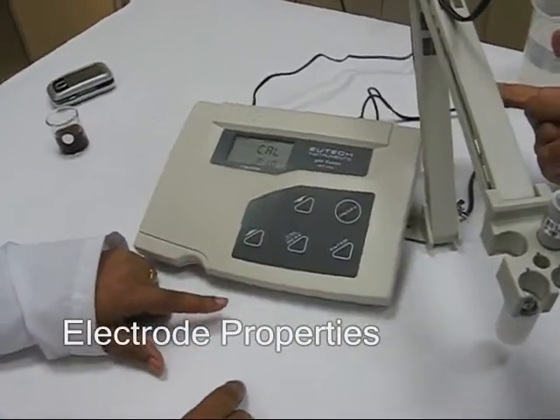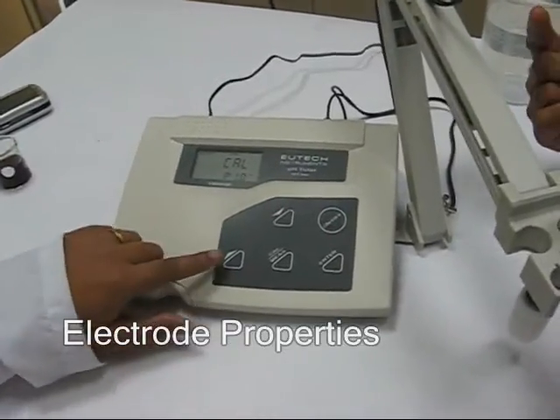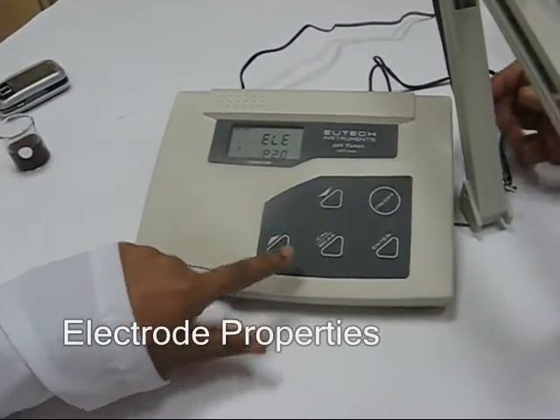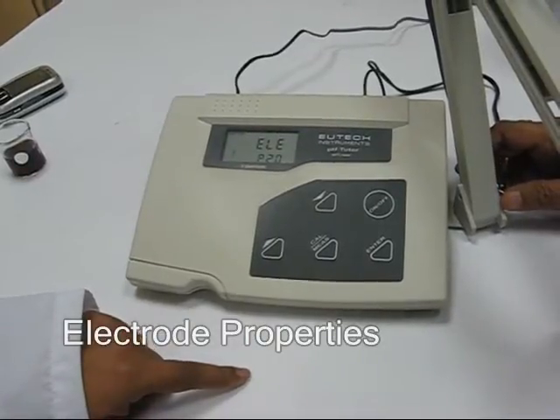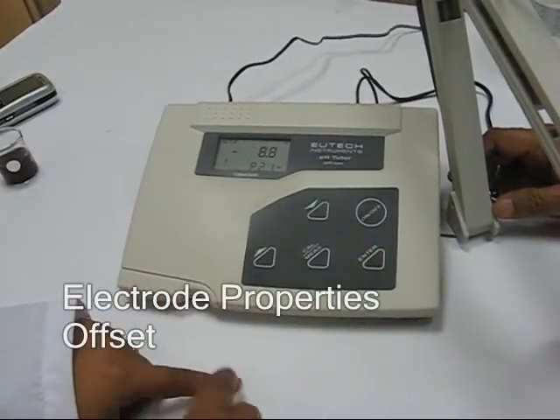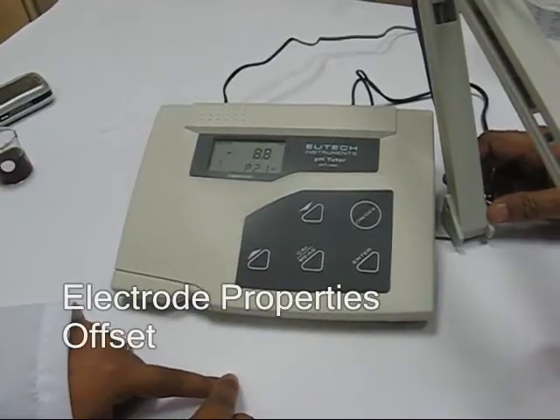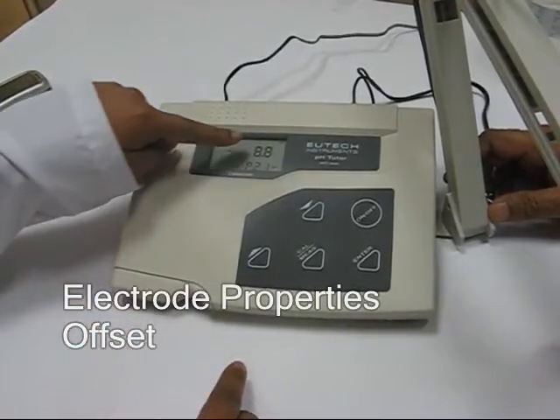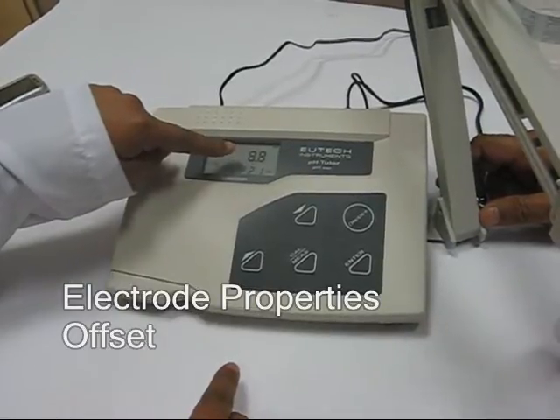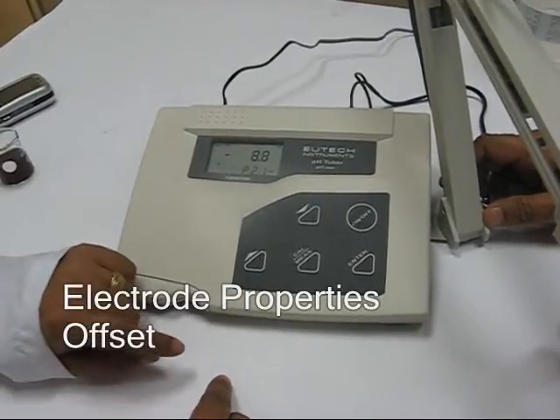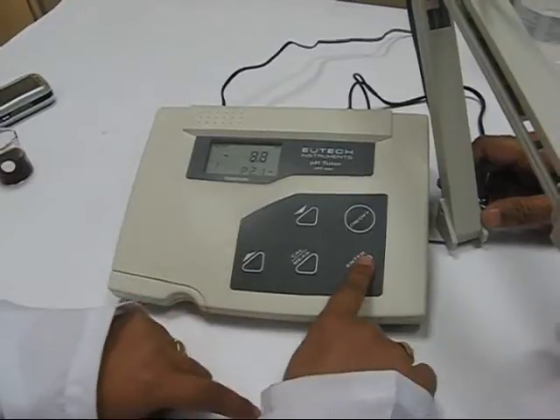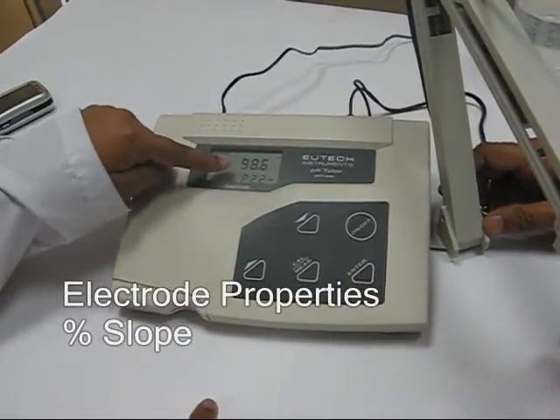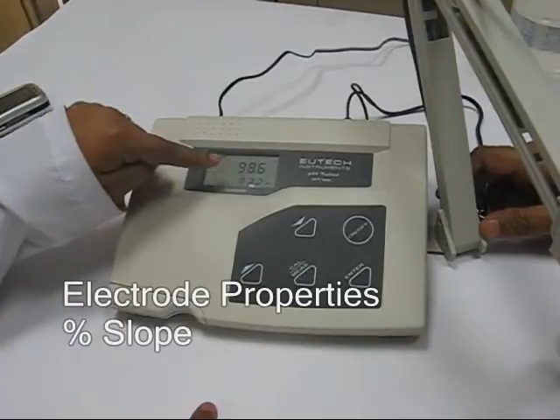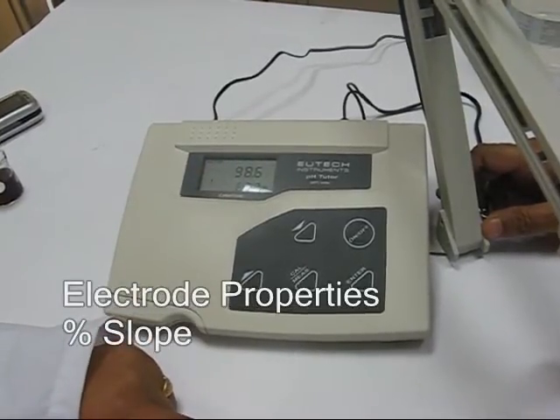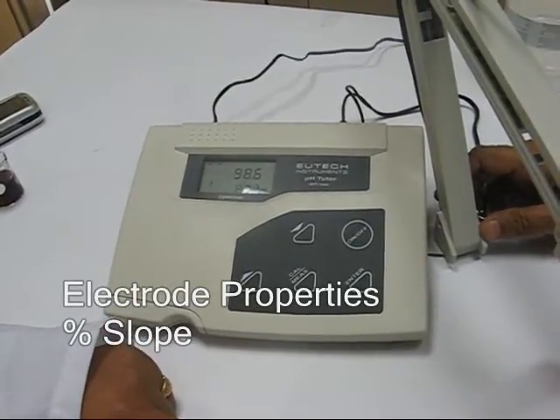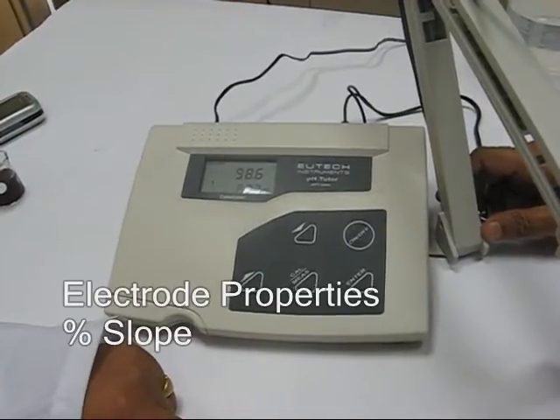Now. That's 1.0. Yes. The menu is in 2.0. So you press the up key. There you go. It says ELE. If you press the enter key now, the first screen says minus 8.8 and there's a millivolt on top. This tells you that the offset of the electrode is 8.8 millivolts, which is a good electrode. Now let's look at the slope of the electrode. Press the enter key. You will see 98.6 there. The 98.6 refers to the percentage slope of the electrode, which is a very good electrode. Yes.